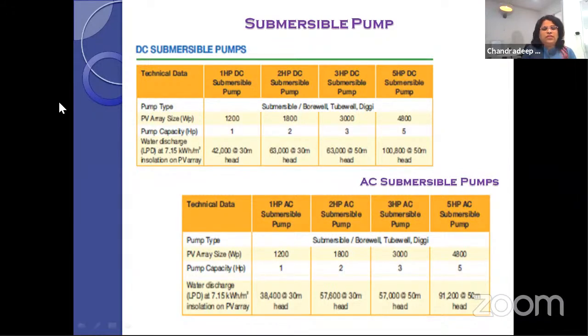So this is a DC. The PV size requirement is 1200 watt peak. To run the 1 HP pump, we need a solar array of 1200 watt peak. In the same way, for 2 HP it is 1800, for 3 HP, 3000, and for 5 HP, 4800. So the pump capacity is 1, 2, 3, and 5. The more important thing is how many liters per day it provides.